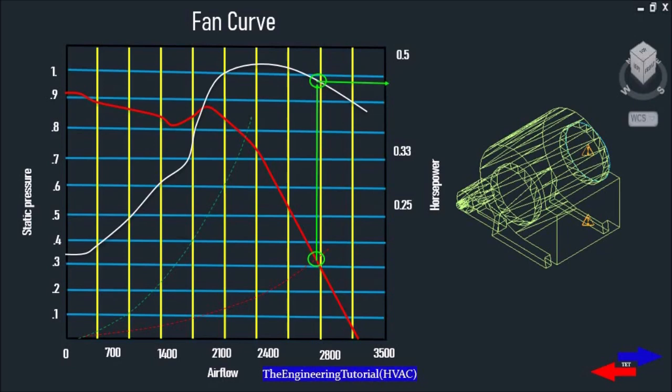Fan curves always slope from upper left down to lower right. The green circle is the intersection of the fan curve which shows the performance of the fan. If you look at the fan curve here, the solid red line is the fan curve that is showing the CFM versus the static pressure.